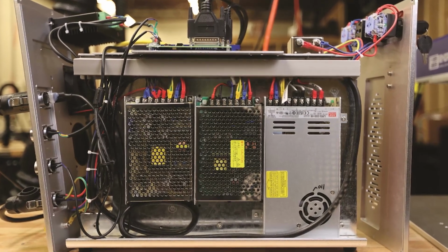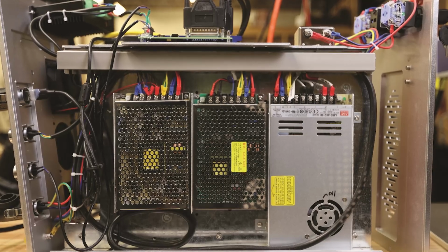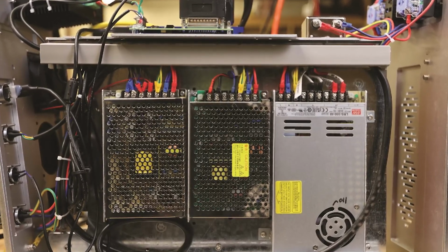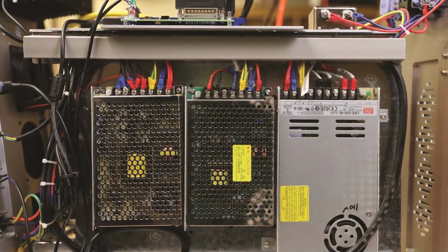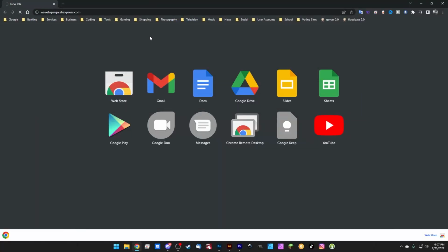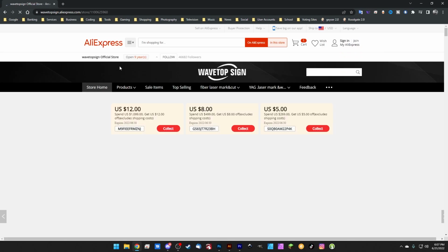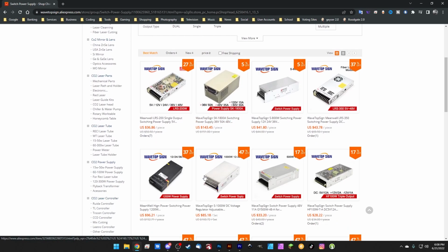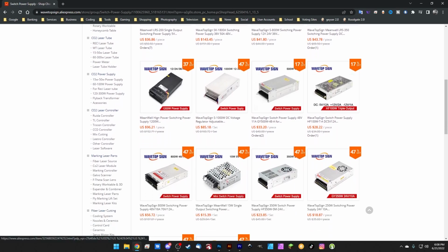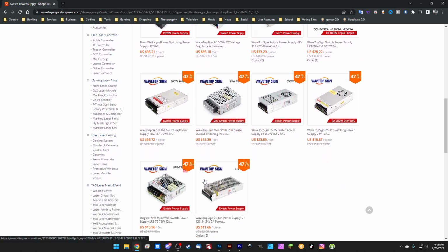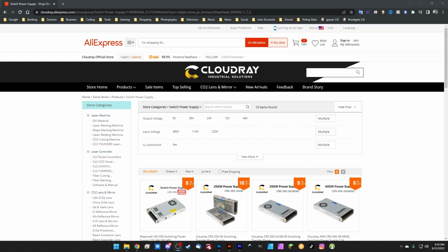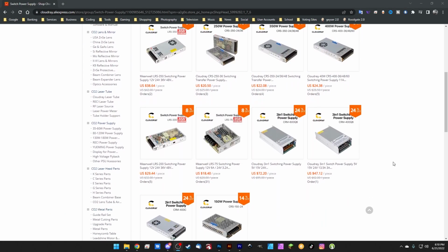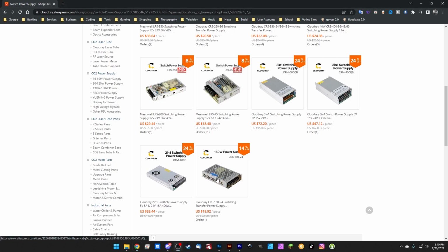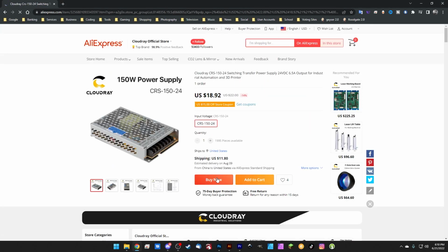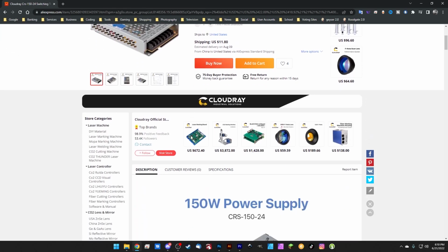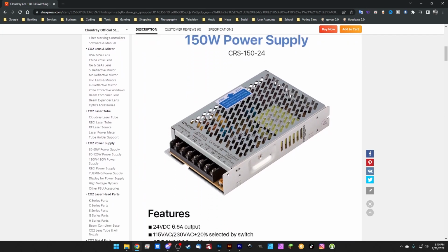Under no circumstance do I recommend ever trying to fix a power supply on your own. They're extremely inexpensive and common, so they're easy to replace. If you discover one of your power supplies is having an issue, simply order a replacement from a trusted company like Meanwell and swap out the unit for a new one. This is the safest and easiest option without exposing yourself to unnecessary risk. If you don't know where to get genuine power supplies, check out the links down in the description and shop wisely. There are many fakes out there that can be shoddy and dangerous. Don't put yourself at risk to save $5 to $10 on a power supply.